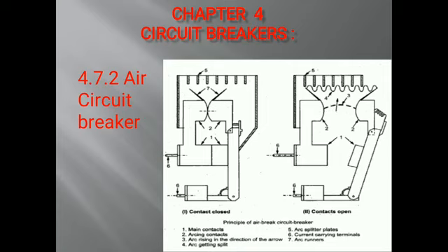They have low resistance and are silver plated. The second pair of contacts is called arcing contact or auxiliary contact. The arcing contacts are hard, heat resistant and made of copper alloy.